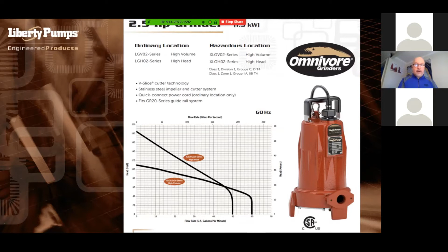We did machine out the cutter plate area a little bit bigger to get us a little bit more flow. So the flow rate on this LGV version, or V for volume, is 60 gallons per minute. And then on the high head version, it's 50 gallons, but the head, it's shut off over 180 feet. So when we're talking grinder pumps now, we talk about the high volume version and the high head version.